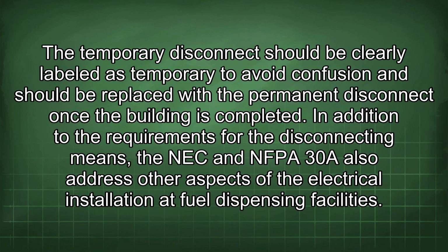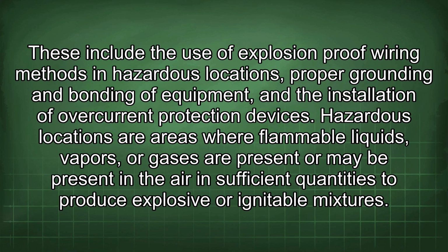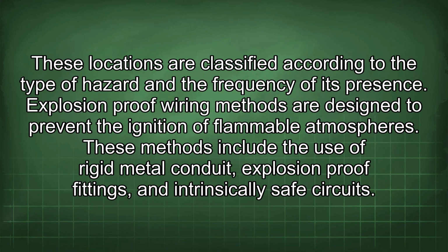In addition to the requirements for the disconnecting means, the NEC and NFPA 30A also address other aspects of the electrical installation at fuel dispensing facilities. These include the use of explosion-proof wiring methods in hazardous locations, proper grounding and bonding of equipment, and the installation of overcurrent protection devices. Hazardous locations are areas where flammable liquids, vapors, or gases are present or may be present in the air in sufficient quantities to produce explosive or ignitable mixtures. These locations are classified according to the type of hazard and the frequency of its presence.